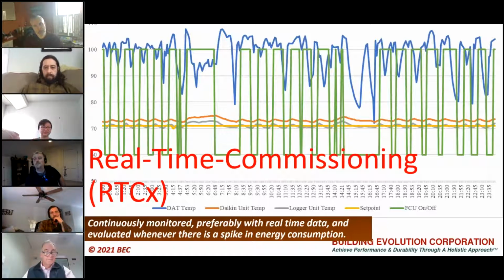Well, that's just on the real-time commissioning. You may see a spike in energy use, but also there could be any number of different parameters that you monitor that signal some type of alarm, and you've got to figure out why that alarm was triggered. Yeah, it could be energy, it could be temperatures, humidity, CFMs, building pressures. For example, one building that I'm helping out with right now, it's actually pressures that we're monitoring, because the building is so sensitive with pipe work that if it gets too high a pressure, they could blow a riser. It's like a high blood pressure building. So yeah, we've got to keep the blood pressure down on it.